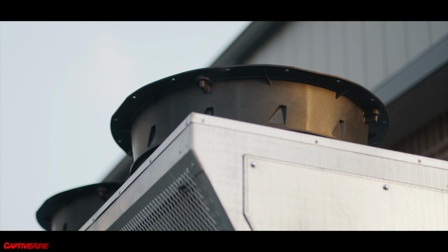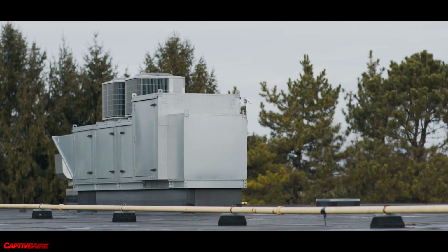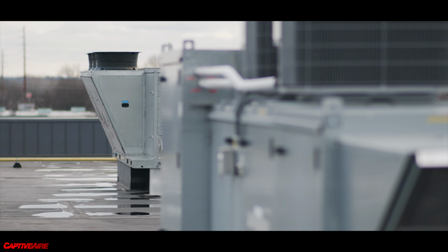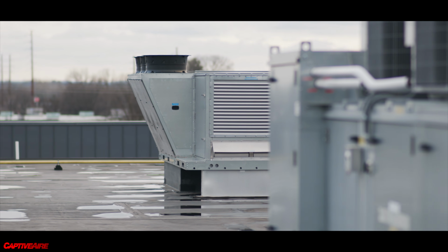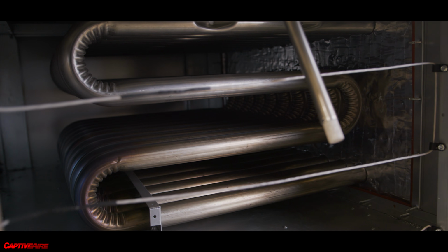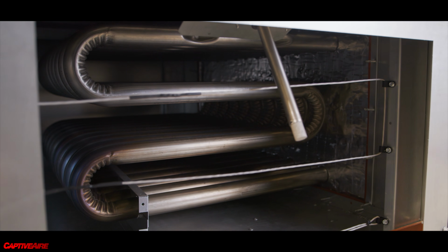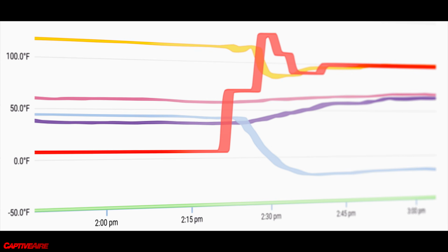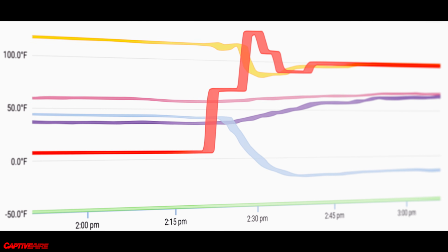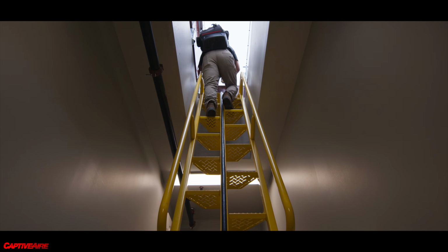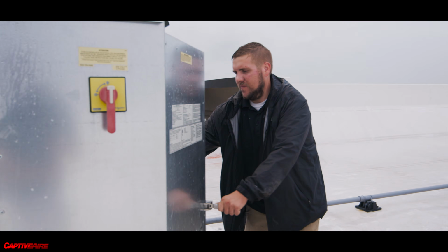This was at a time when the outside air temps were negative 20 degrees. And with that dedicated makeup air unit down, we were able to make up that same amount of outside air on the Paragon, which had enough heat to still maintain those discharge temps. It got us by. We changed the operation of the unit from how it was intended to operate, but we could see what the root cause was and get them to a point where we could keep them running until we can get a tech out there to actually repair the final resolution.